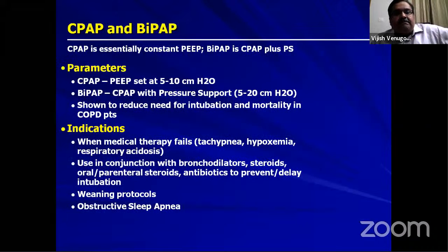Coming to CPAP and BiPAP, again, CPAP is nothing but a constant PEEP, and BiPAP is CPAP with pressure support. So pressure support is applied only during the inspiratory phase. Now CPAP is PEEP set at around 5 to 10 centimeters of water, and BiPAP is CPAP with a pressure support. So pressure support you can set from 5 to 20 centimeters of water. And this is shown to reduce need for intubation and mortality in COPD patients.